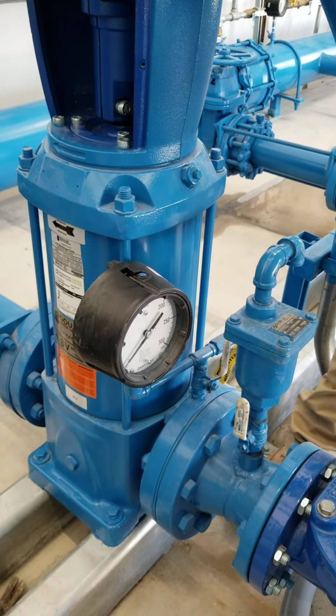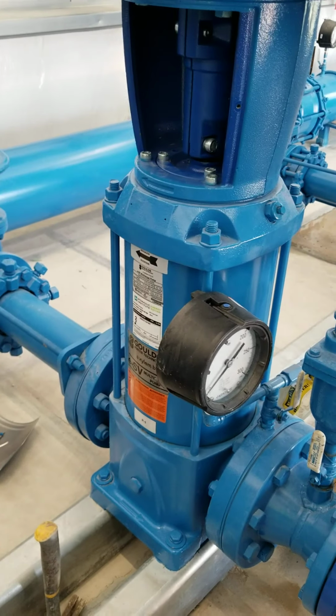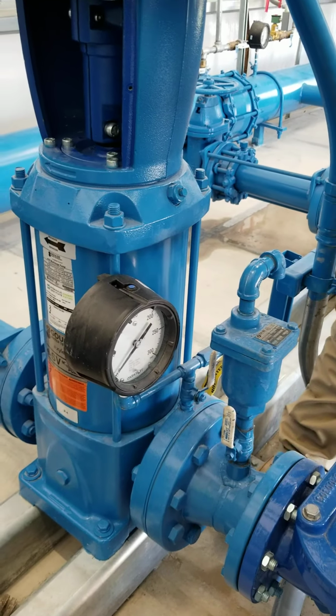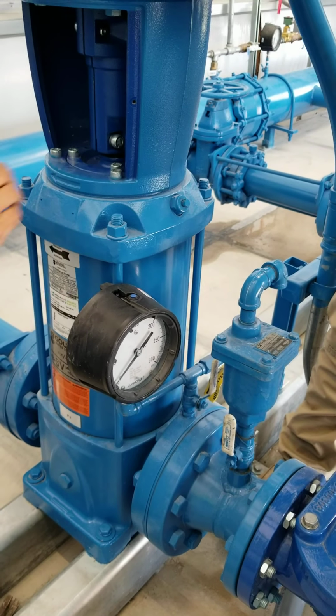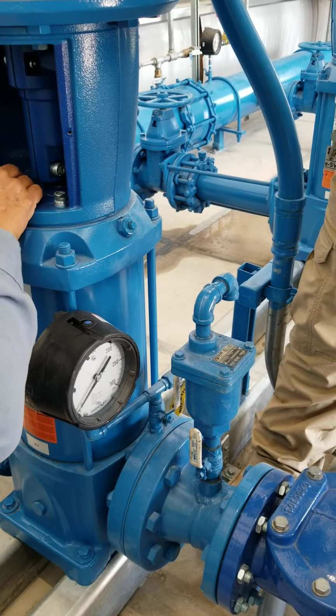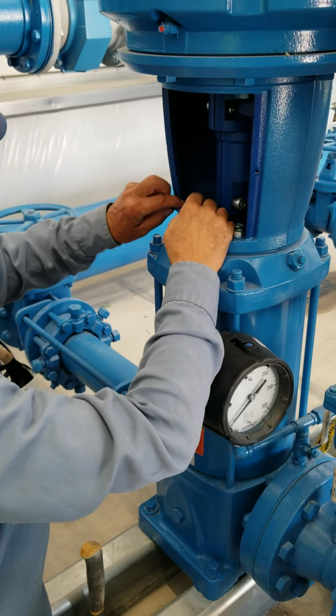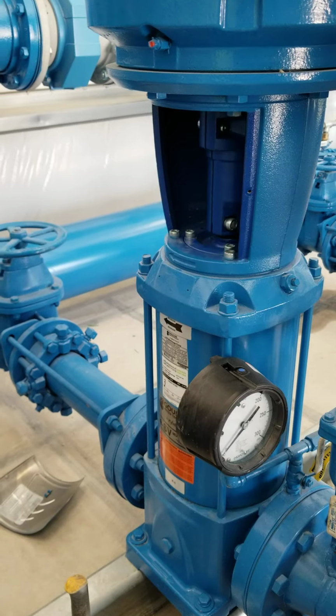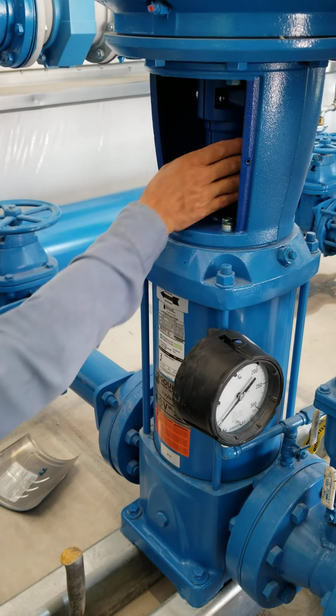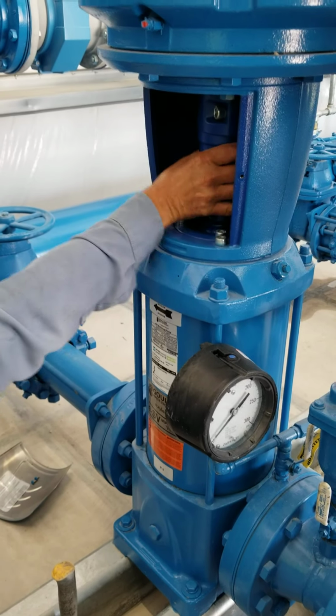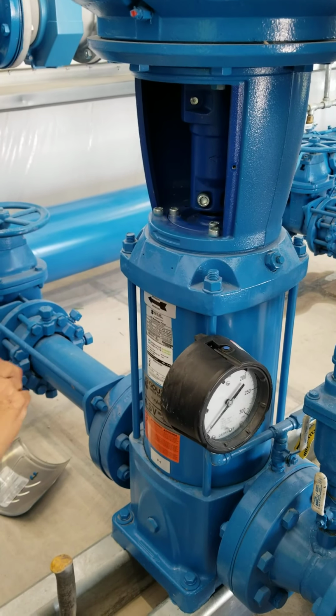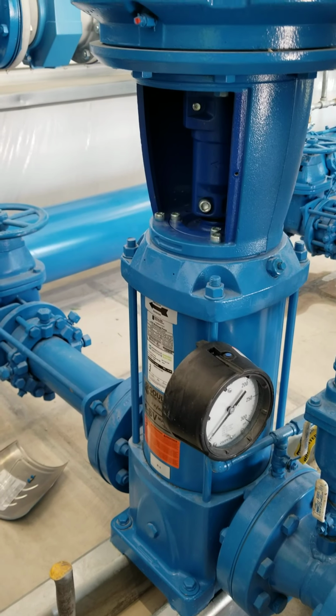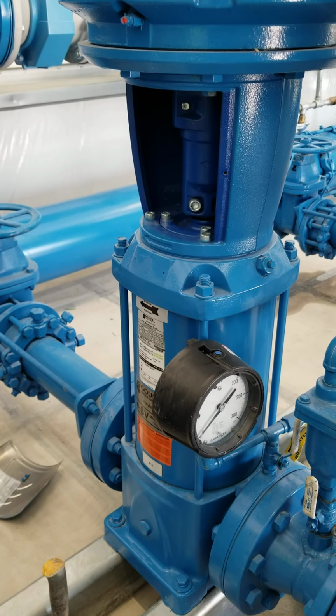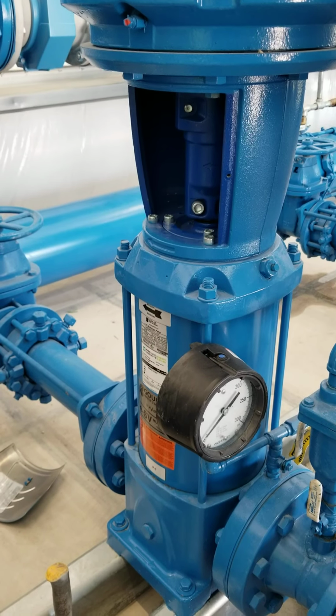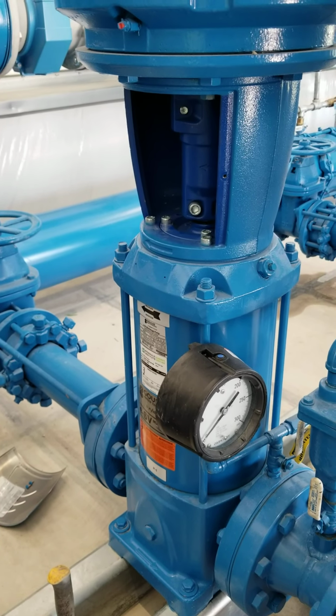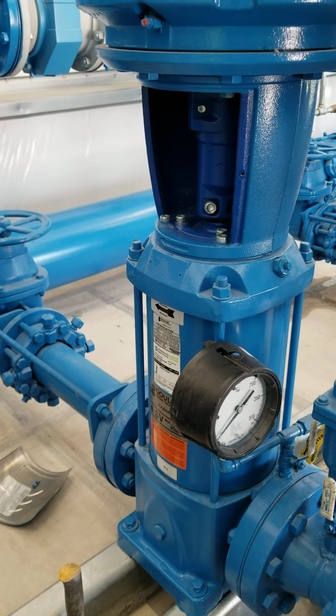No, it's not. They're very user friendly, and the biggest problem for these is air. You can't really over tighten and mess up out here either, especially if you have this in there, it'll stop you. Now, with another style of pump we sell, the gap is a little smaller, and as I'm putting it back together, I keep spinning it to make sure I'm not getting any drag, because there's been times where I've used that spacer and I still could feel some drag. So then you just got to go in there and get it to where you have no drag, and then see what your flow is. But normally it's not even that noticeable.